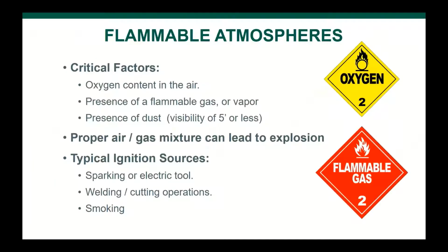So let's look at flammable atmospheres. As we already talked about, the oxygen content in the air is really critical if it's more than 23.5%. There might also be the presence of a flammable gas, a vapor, or the presence of dust. So there's a certain mixture of gas and air, depending on the concentration of oxygen, that can lead to an explosion. And you have typical ignition sources: your electric tools, sparking, welding, cutting operations, smoking, believe it or not.